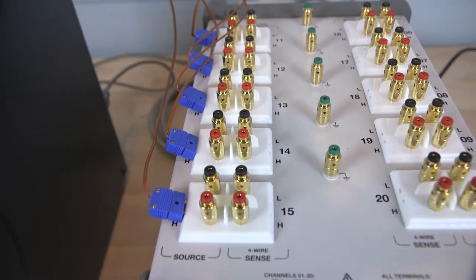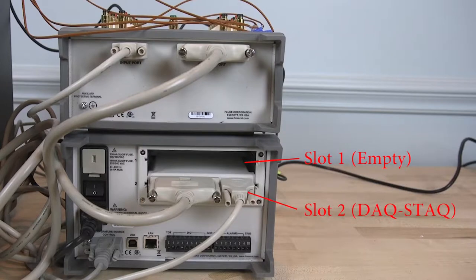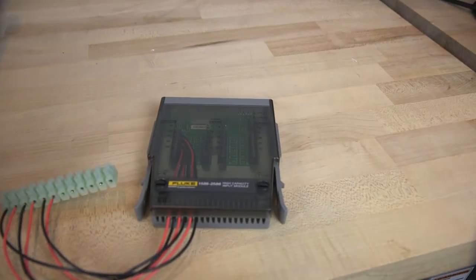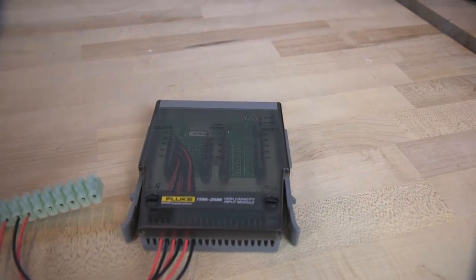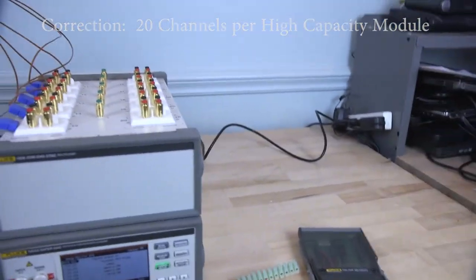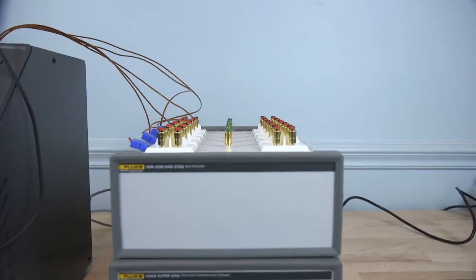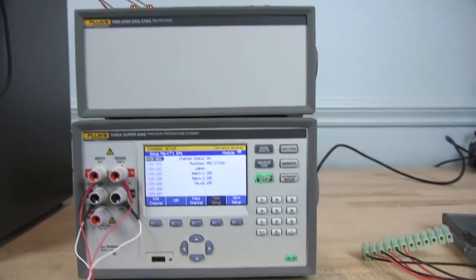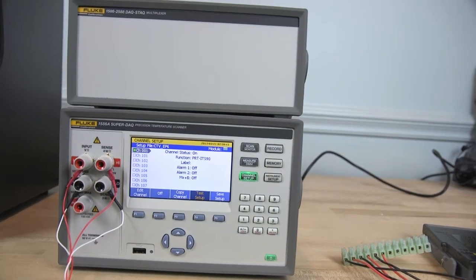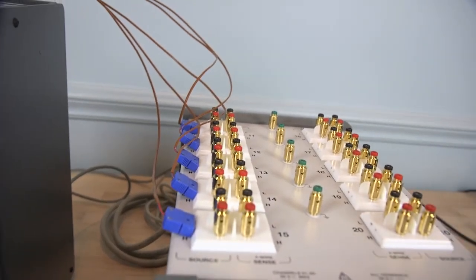Let me show you the DAQ-STAQ connection box. There are actually two slots on the back of the 1586A. You can have either a DAQ-STAQ in that slot — there's a control board that goes into the back of the 1586A — or you can use a high capacity input module, which can take 40 channels itself. You can have a mix of these two, or two DACStacks, or two high capacity cards. Right now I just have the DAQ-STAQ control board in the 1586A, and that's what we're going to use for multiplexing these five thermocouple sensors into the DAQ-STAQ.